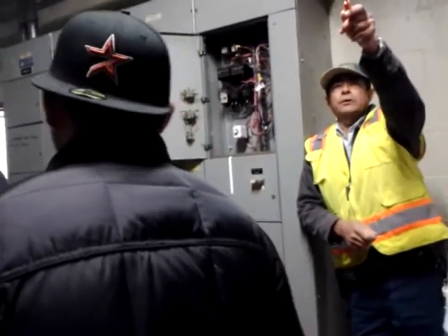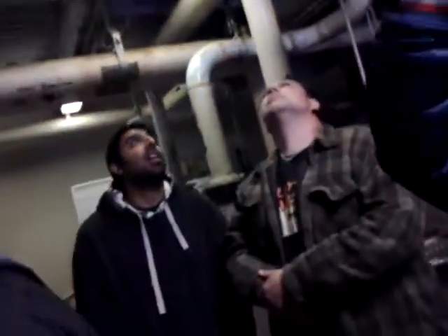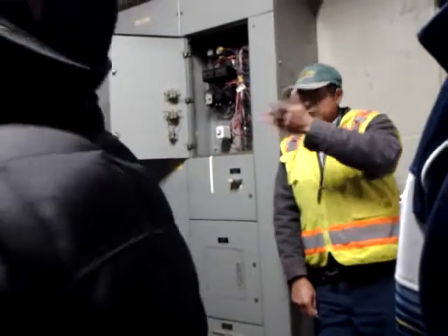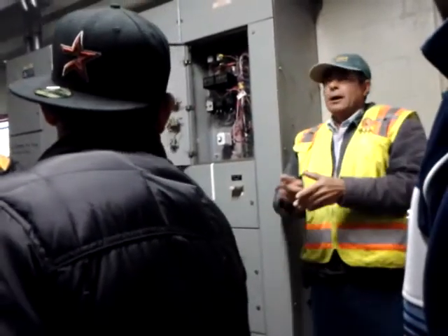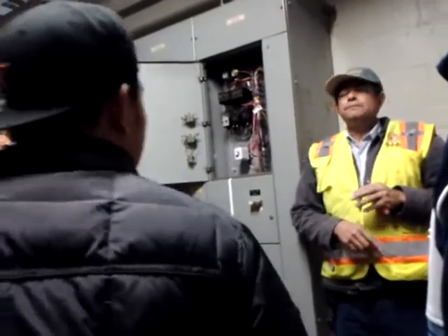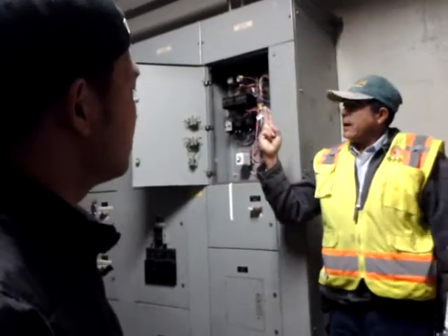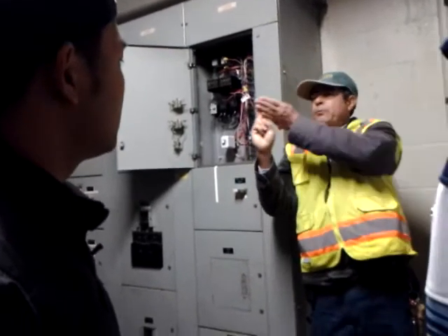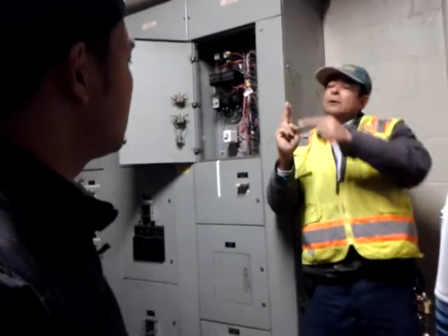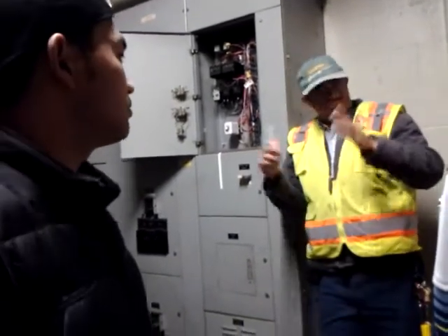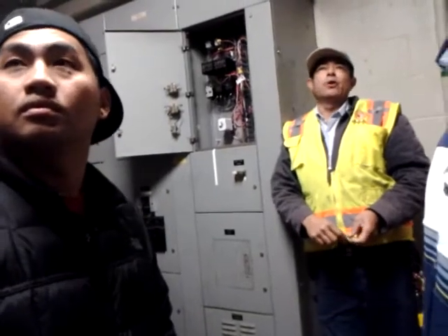Now, I don't know if you guys can see that little square thing up on this slide, right above your head. Right there, that little square box. What that is, it is a water flow sensor. It has a little paddle. It's still a mechanical device. The pump moves water, and it has a little paddle that is probably about an inch wide. As the water pressure hits that paddle, it's pushed and it closes the switch. Very simple. Nothing electronic about that.